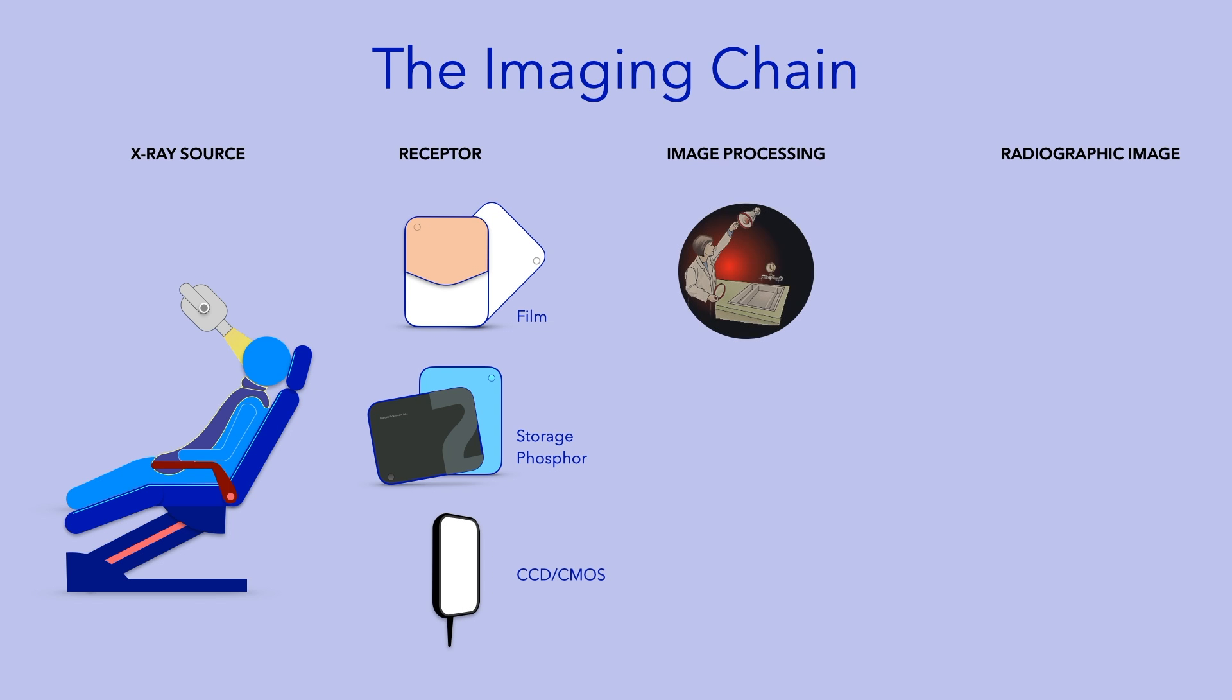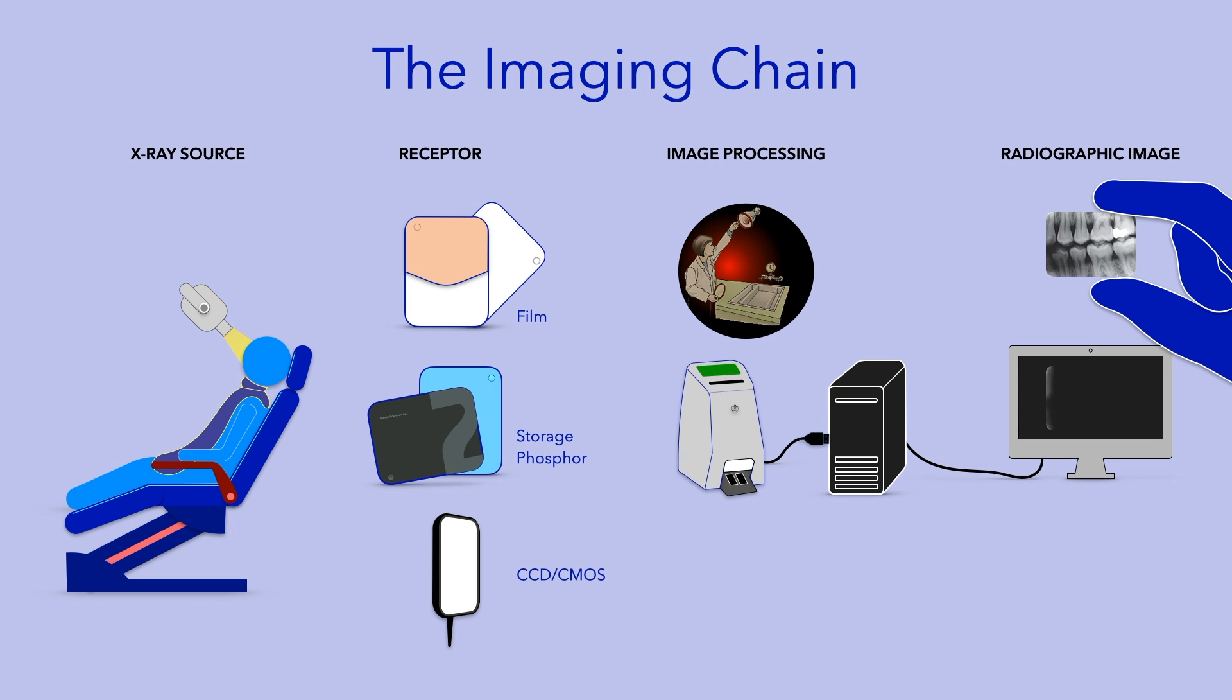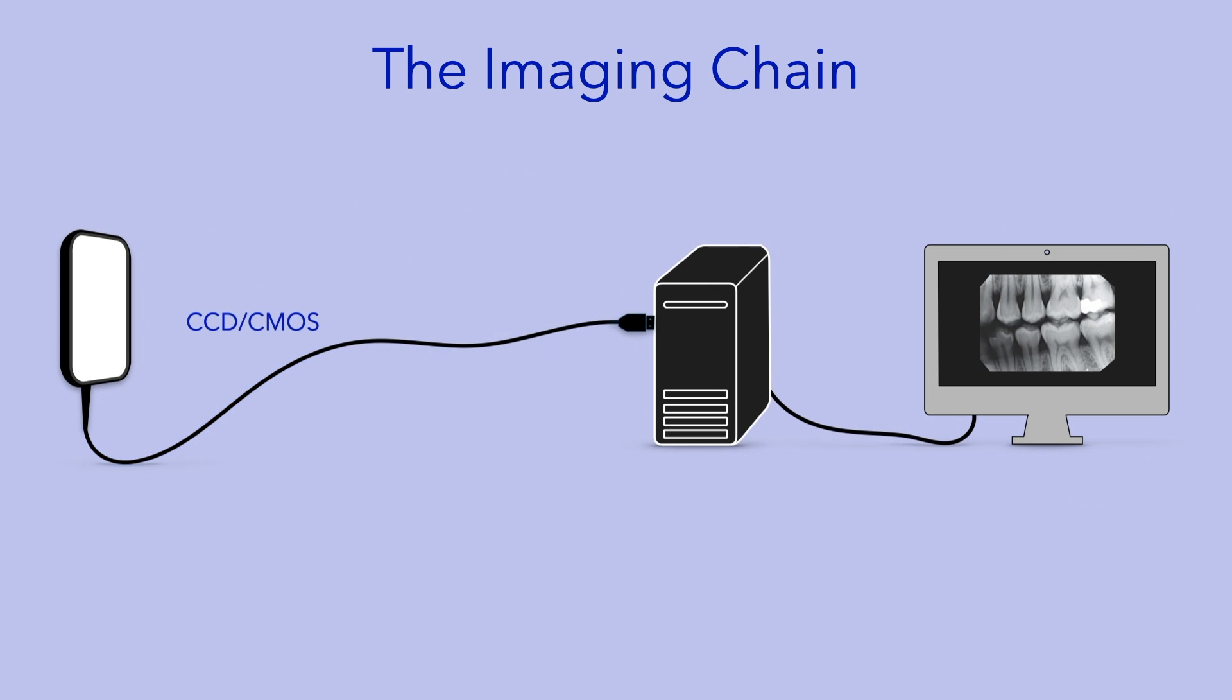Following exposure, radiographic film undergoes chemical processing to make a physical radiographic image that can be handled. Image formation with storage phosphor or CCD or CMOS-based technologies involves computer processing to make a digital image. Thus, the latter two technologies are referred to as digital imaging, while film is referred to as analog imaging. This video will focus on the use of CCD and CMOS-based technologies in dento-maxillofacial imaging.